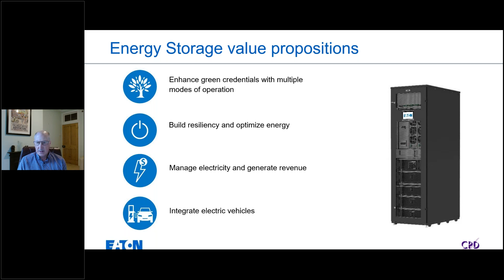Just to explain the little image we have on the right-hand side here, that's our X-Storage compact system. It's an all-in-one system. We see a single rack here. This is up to 40 kilowatts, 50 kilowatt hours in this 600 by 1000 footprint. We can add a second rack with a second or third string of batteries in, so that would become 40 kilowatts, 50, 100 or 150 kilowatt hours. And then we can parallel up to 5 power converters, each of which can have 1, 2 or 3 50 kilowatt hour battery strings attached to it. So up to 200 kilowatts with 250, 500 or 750 kilowatt hours of stored energy capacity.